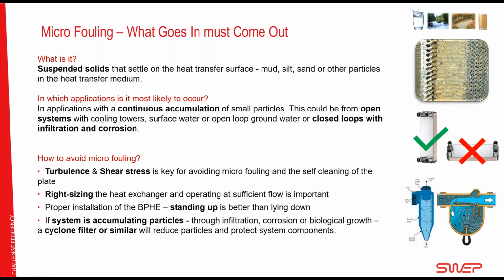Again, open loop systems return here as a risk factor. Also, open loop groundwater loops, when you dig it down in the ground and get up, if you start to leak in clay and other things. Another one is closed loop with infiltration, if they're old and broken and you start to have infiltration of bad water, or even corrosion of gray steel pipes that will start to corrode, you can have this accumulation of small particles. How to avoid it? We will look more into detail next slide on turbulence and shear stress, but that is very, very important. What comes in must go out.